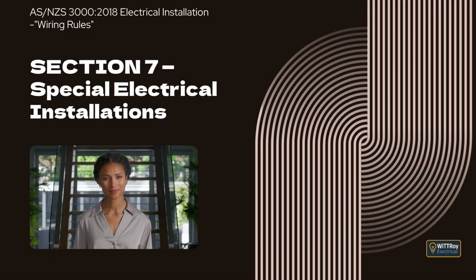Clause 7.3.8.2 Grid-connected inverter systems. This clause introduces requirements for inverter systems connected to the electricity network. Clause 7.3.8.2.1 General. This clause explains that connection of a grid-connected system is subject to formal agreement with the electricity distributor. Clause 7.3.8.2.2 Switching. This clause explains that a main switch must be provided to allow isolation of the inverter output from the switchboard to which it is connected, and that all switches must be clearly identified according to their function.